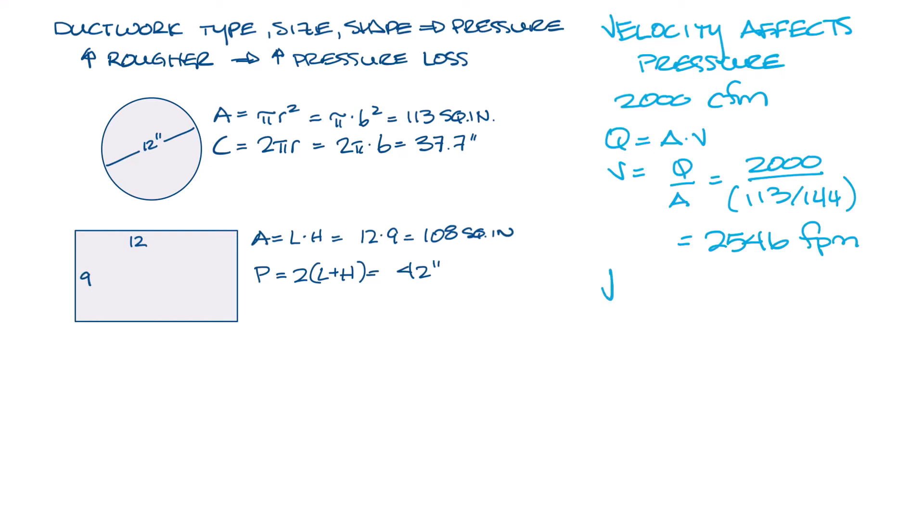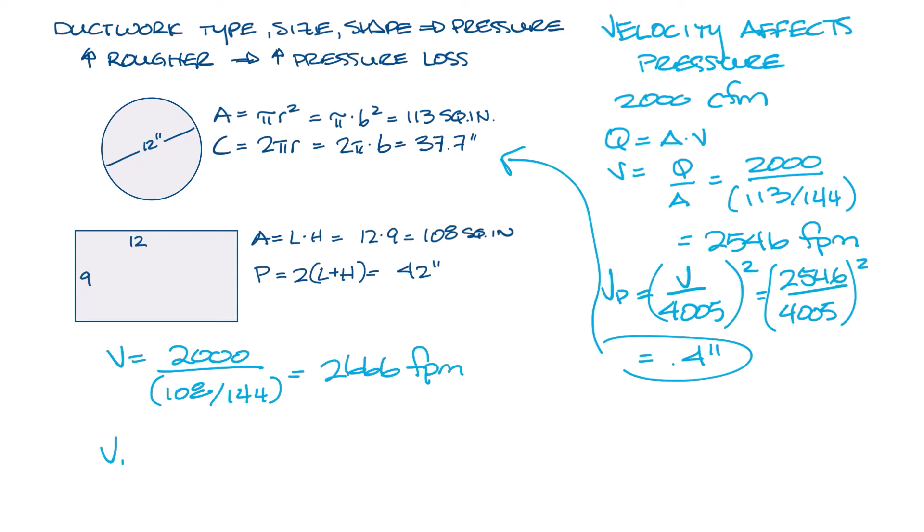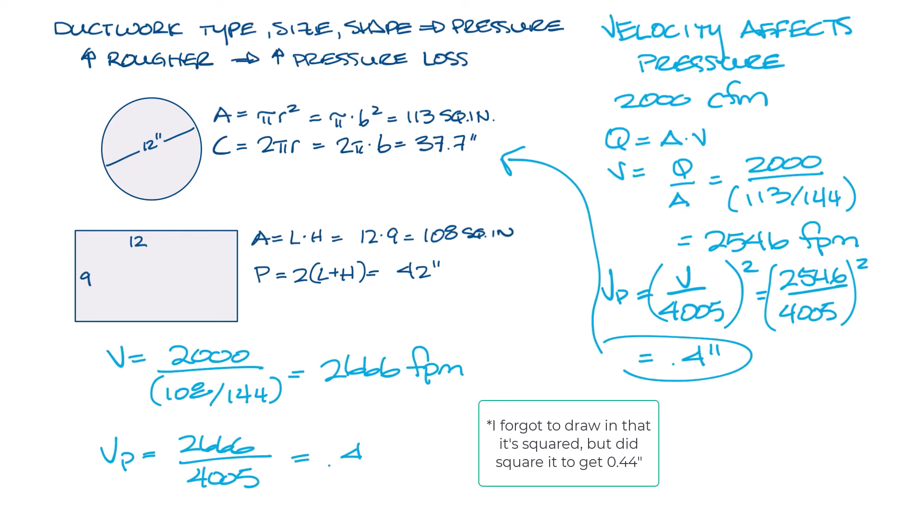The velocity pressure equals velocity divided by 4005 squared. So that comes up to 2546 divided by 4005 squared, and that equals 0.4 inches. Now let's do the same for the rectangular ductwork. We have velocity equals 2000 divided by 108 divided by 144, which is 2666 feet per minute, and then the velocity pressure is 2666 feet per minute divided by 4005 and square all that, and you get 0.44 inches for the rectangular ductwork.